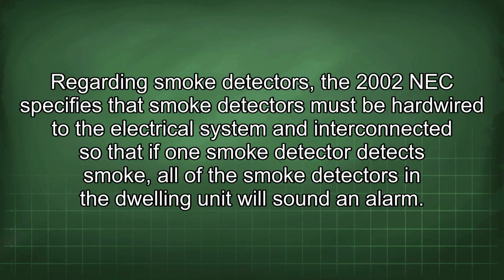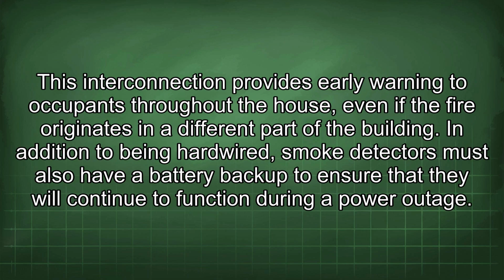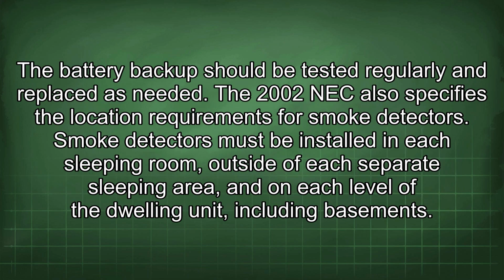Regarding smoke detectors, the 2002 NEC specifies that smoke detectors must be hardwired to the electrical system and interconnected so that if one smoke detector detects smoke, all of the smoke detectors in the dwelling unit will sound an alarm. This interconnection provides early warning to occupants throughout the house, even if the fire originates in a different part of the building. In addition to being hardwired, smoke detectors must also have a battery backup to ensure that they will continue to function during a power outage. The battery backup should be tested regularly and replaced as needed.